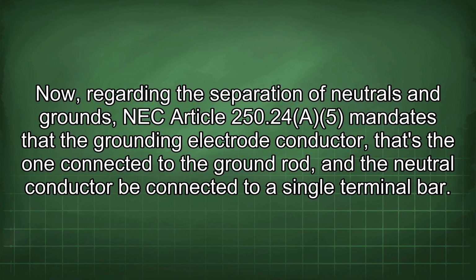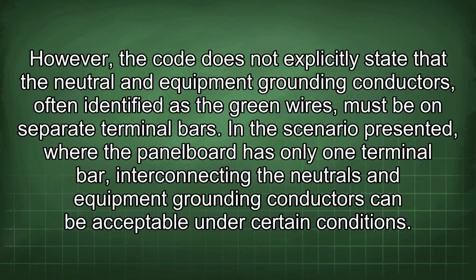Now, regarding the separation of neutrals and grounds, NEC Article 250.24 mandates that the grounding electrode conductor, that's the one connected to the ground rod, and the neutral conductor be connected to a single terminal bar. However, the code does not explicitly state that the neutral and equipment grounding conductors, often identified as the green wires, must be on separate terminal bars. In the scenario presented, where the panel board has only one terminal bar, interconnecting the neutrals and equipment grounding conductors can be acceptable under certain conditions.